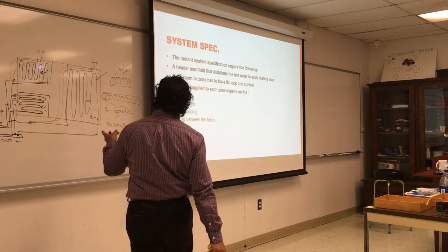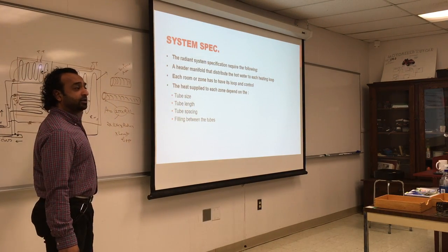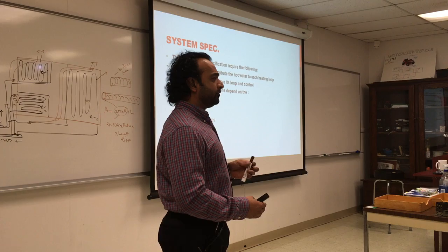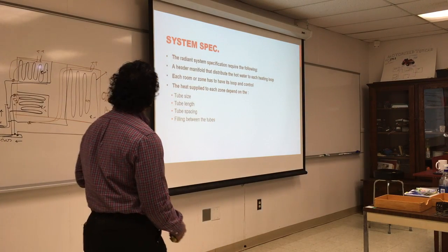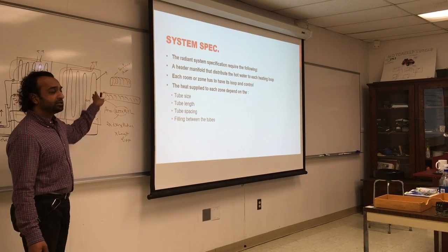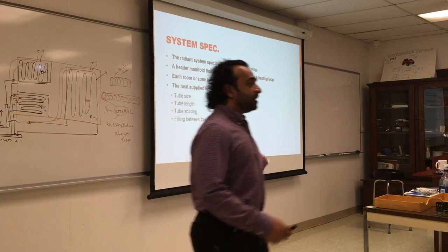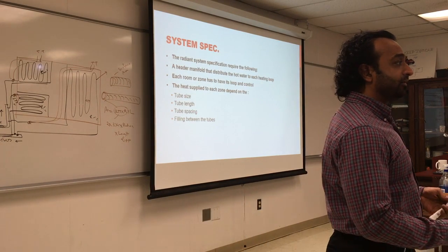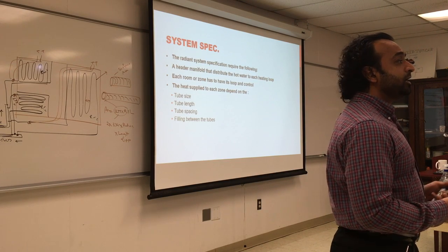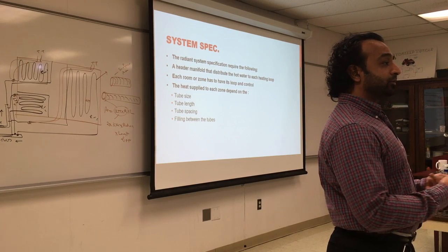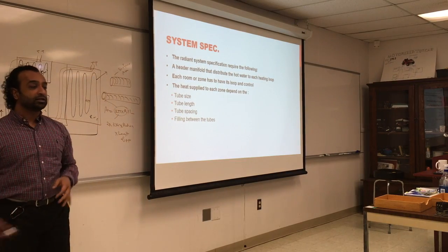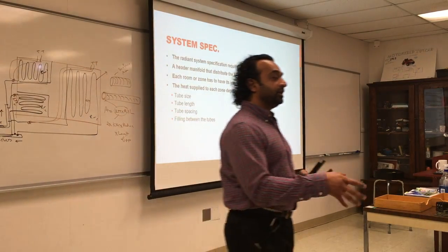So you want the velocity to be slower, between 3 feet per second and I think 1 foot per second for those tubes. So again, the velocity matters, the size matters, and the space between the tubes matters, because on the inside the filling also matters. If you don't have any filling, then you'll have a lot of air in there, and air is okay, but you have to put in more heat. If you have gravel, I've seen some gravel conduct more heat. Eventually, you want the floor to be a uniform temperature when you go and scan it. You want to reduce the heat spots.